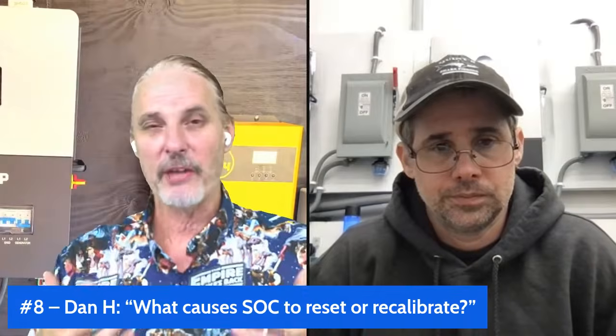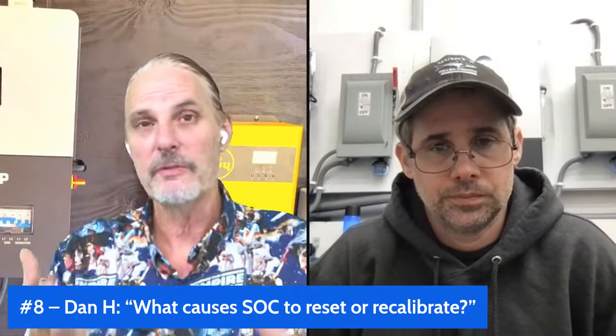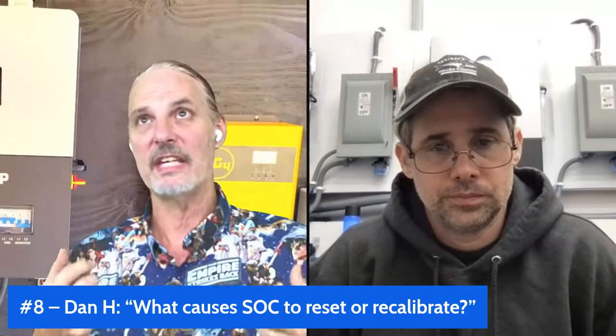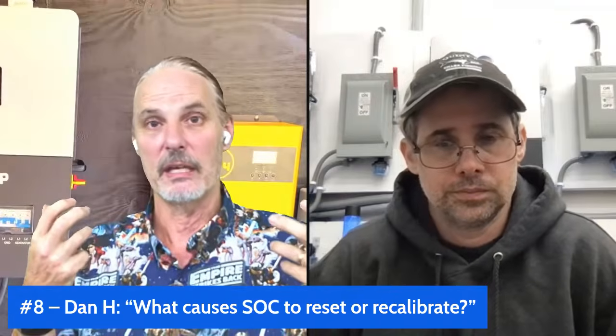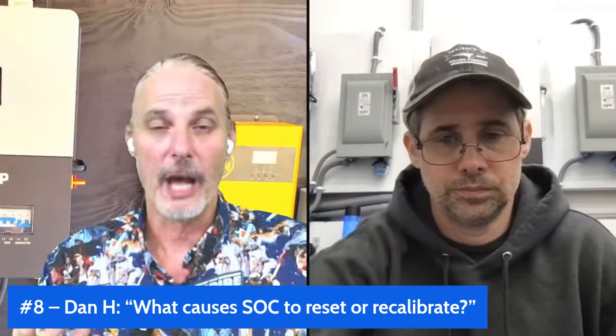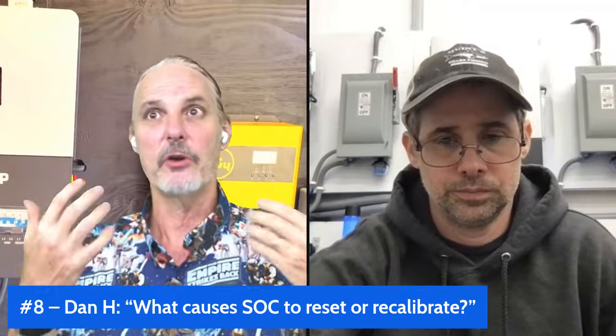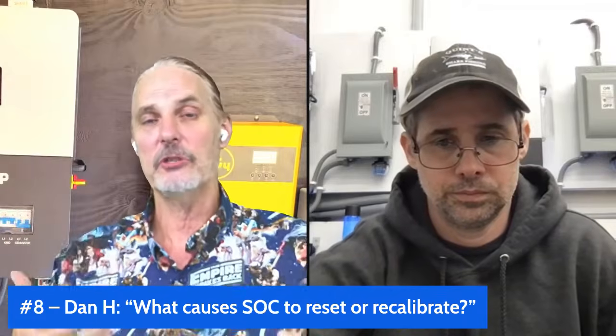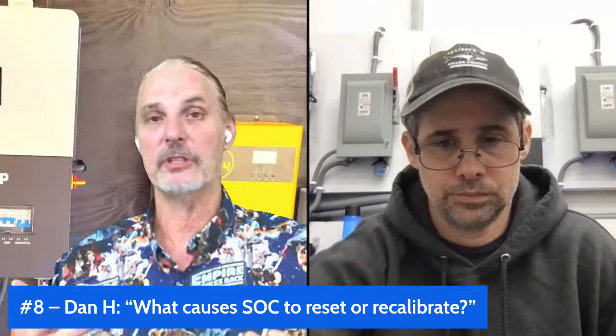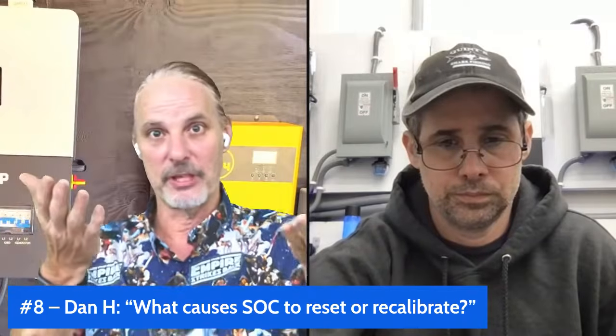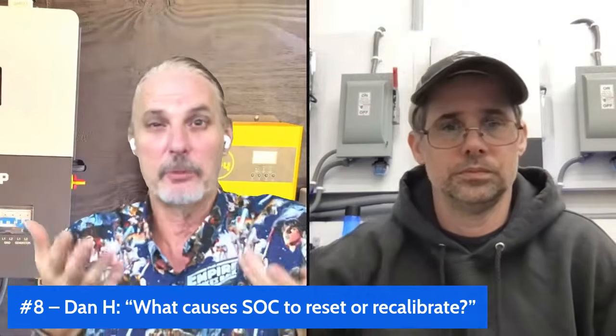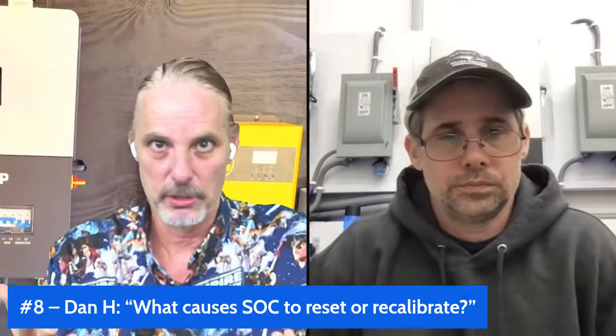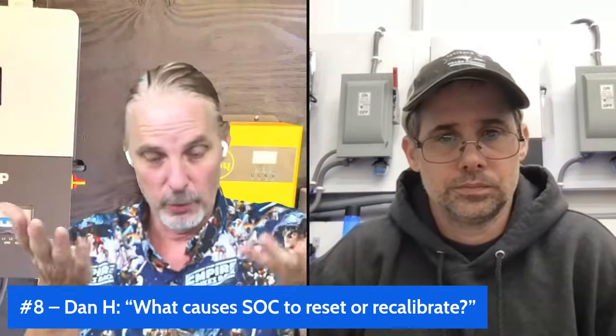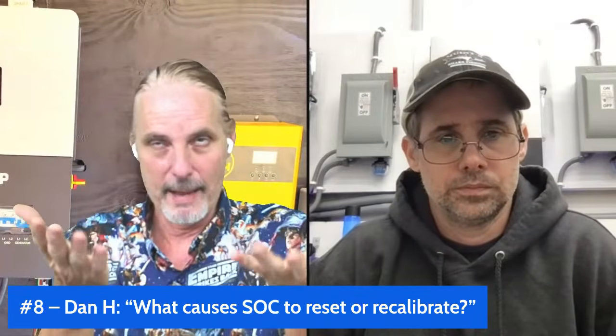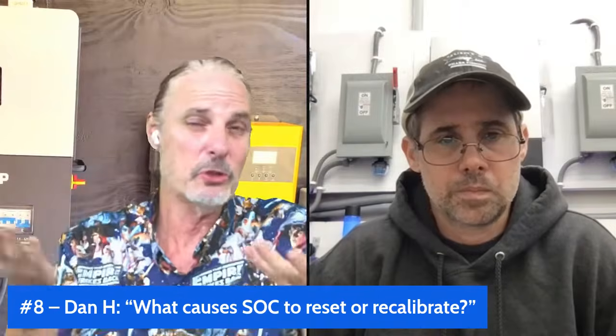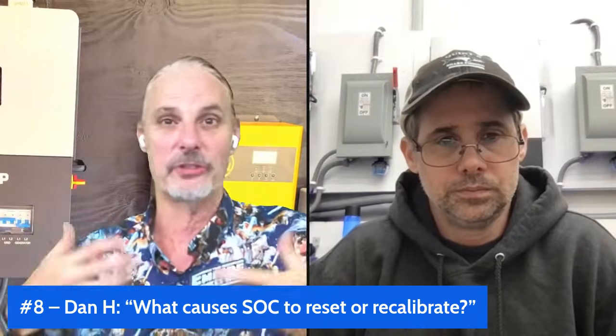Once it gets up there, most batteries won't reset until the absorption stops. What I mean is they'll continue taking power and amps in, and when that amperage drops and they stop absorbing — when they get fully saturated with power — the current going into the battery drops, and usually below 1 or 2 amps is considered fully charged.